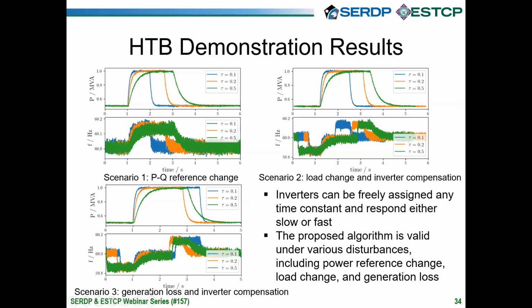The third case is the generation loss case. Initially there's a generation drop, so the frequency drops, and later the generation is back, so there's a frequency jump. For both cases, you can see that the controller performs as expected, bringing the frequency back, and the corresponding power change follows the predefined ideal curve.